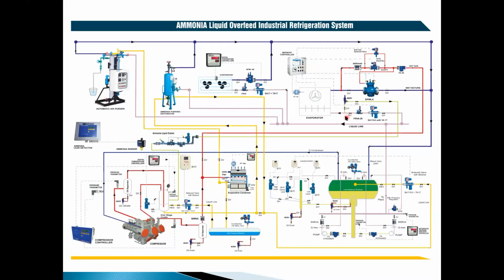Another function of this flow control valve, also called the metering valve, is that you can set the flow required into the evaporator depending on your evaporator capacity. So individual evaporators can have an individual flow. Even though the outlet flow of the pump is the same, you can have a different flow into different evaporators, and irrespective of the variation at the inlet of the flow, the outlet of this flow remains constant. So what we have is a liquid feed, a wet return line. We have a solenoid valve in the wet return line. We have a supply solenoid valve in the hot gas line.